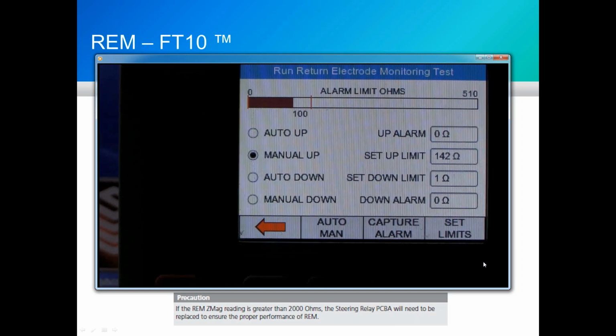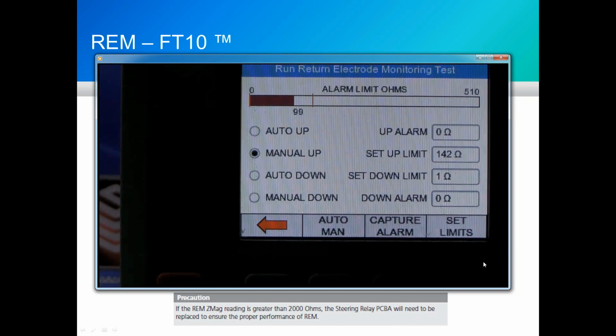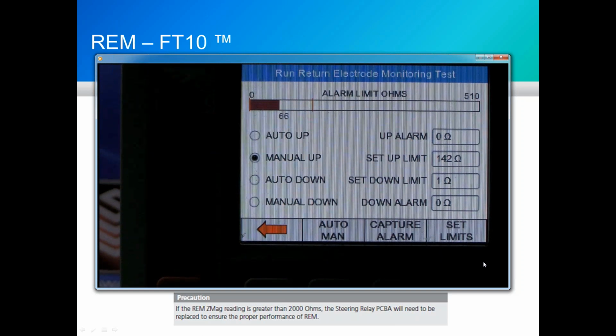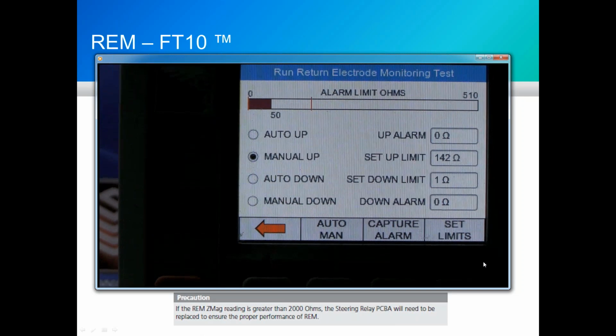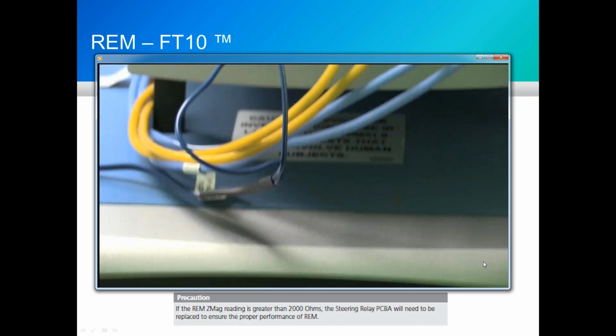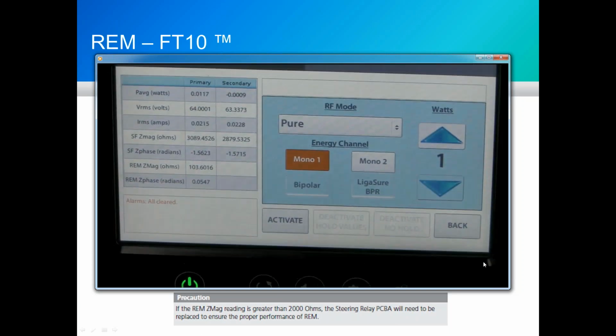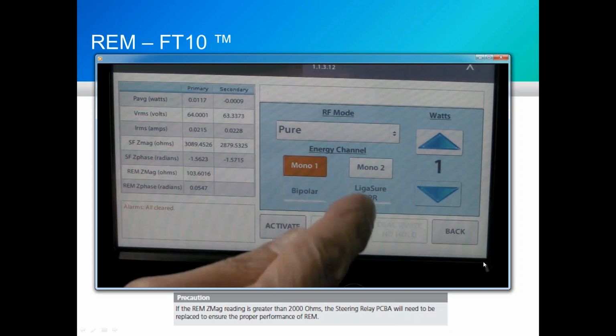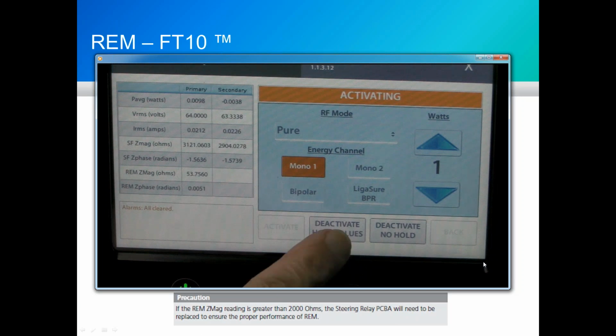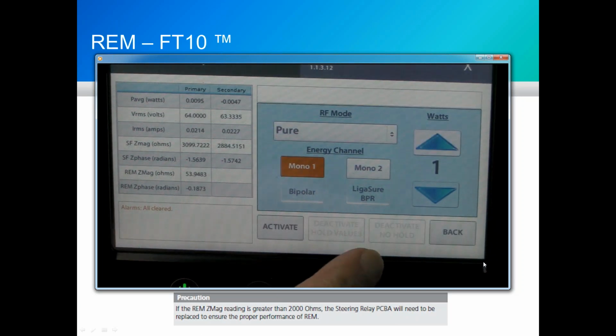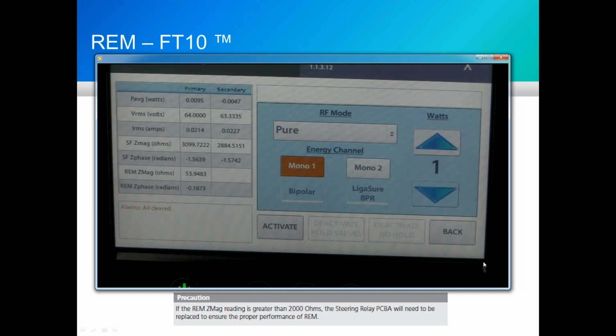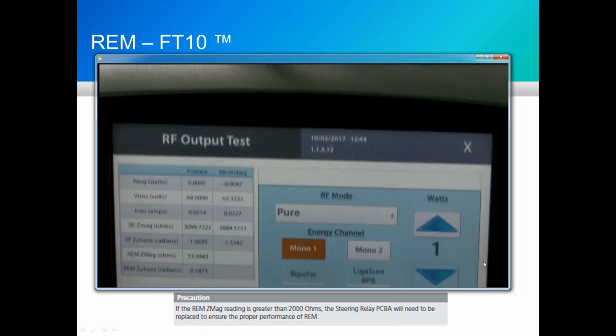Now I'm going to decrease the resistance down to 50 ohms. This screen that we're seeing on the FT10, when you're in service mode on the Triad, this was actually the center screen, but we never really paid a whole lot of attention to it. There are two measurement points internal to the FT10. You see that we measured 54 ohms in this case.